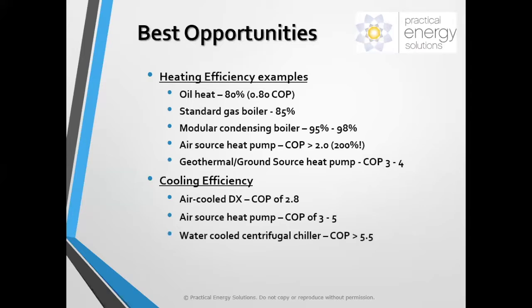A water-cooled centrifugal chiller has a coefficient of performance over 5.5. We often recommend that for buildings where there are a lot of terminal units, like fan coil units, already in place. And here you are at over 550% efficiency with that central chiller. Often we recommend that in places where there's a campus and there are multiple buildings, and that central plant chiller can actually provide cooling to multiple buildings. And it runs really efficiently at part load as well, whereas the typical sources of air conditioning use just as much energy when it's 78 degrees out and they're cooling as they do when it's 92 degrees out, while a centrifugal chiller can actually scale back and run highly efficiently.